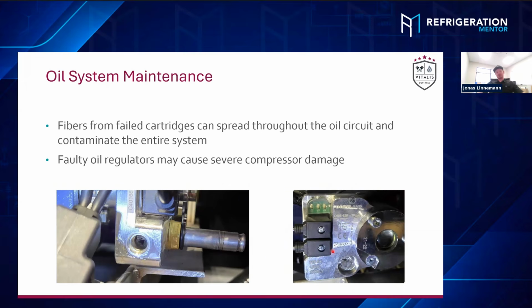But also, if you ever work on a system, it's sometimes good to just look into the sight glass of the oil level regulator. Even if you have some sort of debris inside the valve seat and you see that it's slightly filling, even if it shouldn't fill, that's a good indicator to just open up the solenoid once and check if there's some debris stuck inside the valve seat.